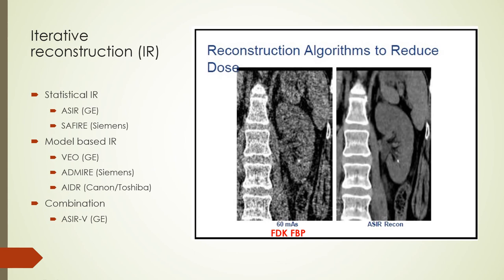Axial and helical acquisitions reconstructed with filtered back projection result in noisy images. Iterative reconstruction methods can produce lower noise images for the same dose. Iterative reconstruction can be done using a statistical approach or a model-based approach; model-based IR produces images with less noise than statistical IR. A combination model and statistical IR approach is also available and reduces reconstruction time. Different strengths of IR are available, often involving blending a percentage of FBP with the IR algorithm, enabling low-dose acquisition with high-quality low-noise images.